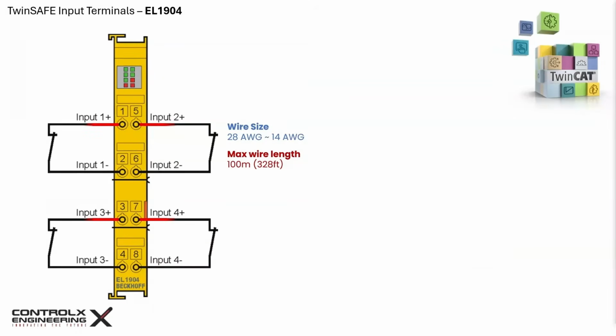The wire length restriction is because the EL1904 inputs use test pulses for cross-circuit detection, as well as to detect shorts to 24 volt or 0 volt. These test pulses are a built-in diagnostic feature that continuously verifies the integrity of your safety wiring and devices. They're essential for achieving the EL1904 certified safety level.